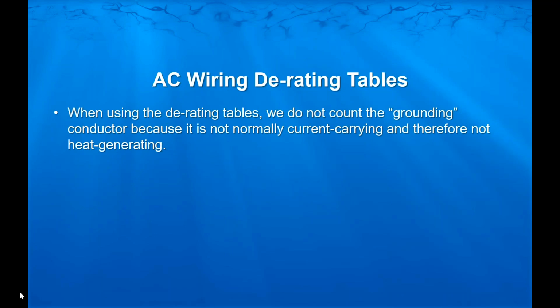So when we use the derating tables, the current carrying conductors that they're talking about, we do not count the grounding conductor. We do not count the green because it is normally not current carrying and therefore will normally not generate any heat.